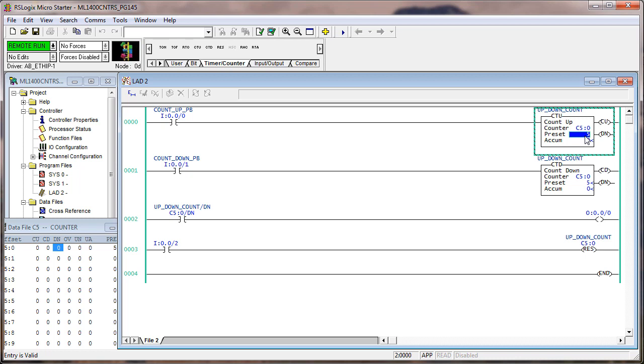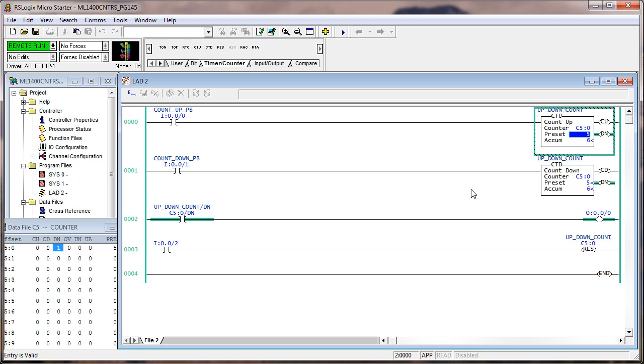Toggle input zero until the accumulate is five or greater, then toggle input one until the accumulate is less than five. Did the done bit clear? Yes. Did the accumulate clear as well? No. The only way you can clear the accumulate value in counter data types is to use the reset instruction or other instructions that directly change the value. Toggle input zero until the accumulate equals the preset, then toggle once more. Did the done bit clear? No. Did the accumulate clear? No.